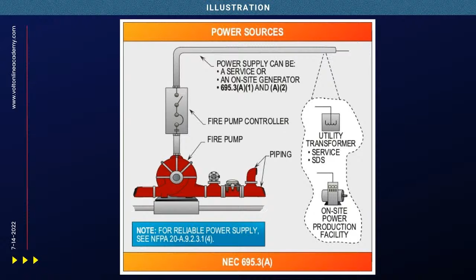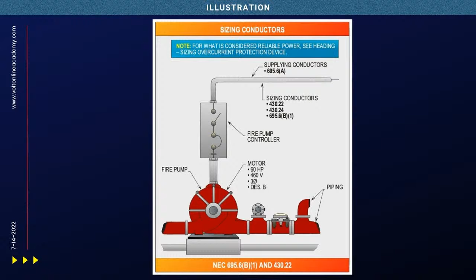Now, one of the things we're going to look at first is sizing the conductors. One of the things everybody has always liked about our illustrations is we give you sections that tie it in. If you look right there where it's talking about sizing conductors, you'll see 430.22, and 430.24, that's if you've got multiple motors. And then 695.6(B)(1), that's going to tie this all together. For this fire pump, the motor is 60 horsepower, 460 volts, three-phase, design B.